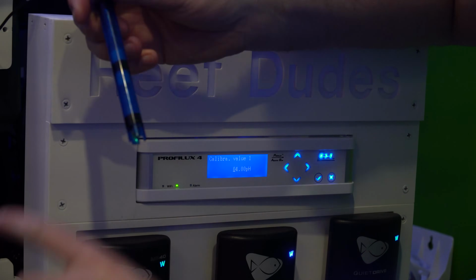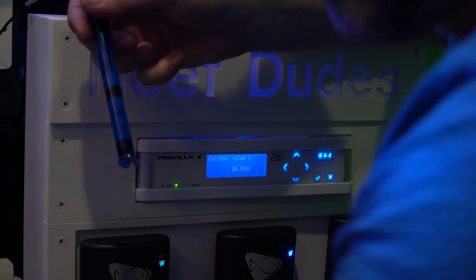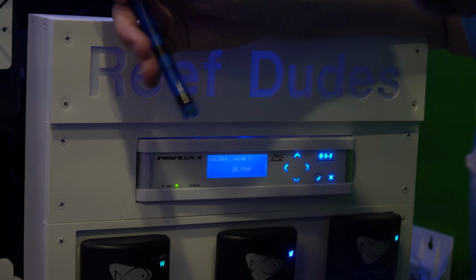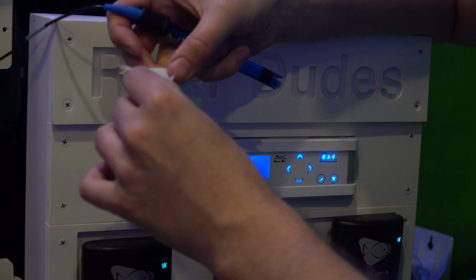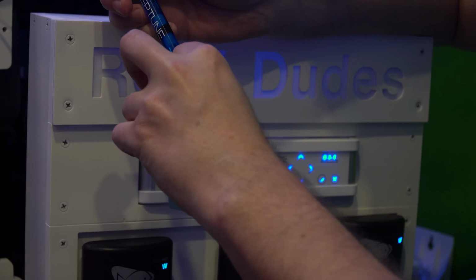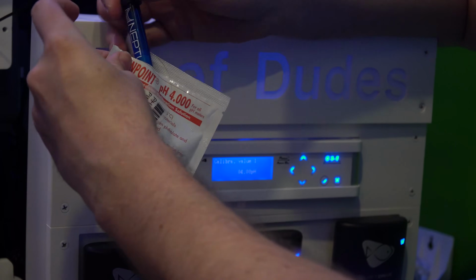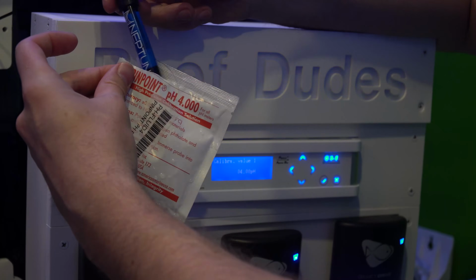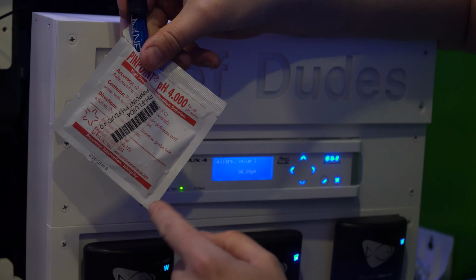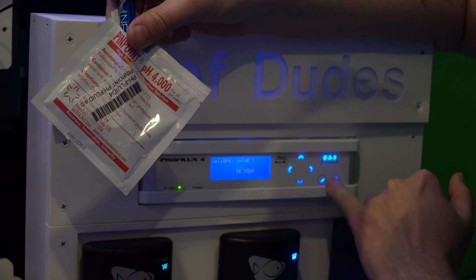All right, let's pull the cap off, and give a quick rinse in RODI water just to get off that storage solution. Open our pH 4 packet and set the probe inside. I usually give a little tap just to make sure you're getting air bubbles off and kind of put it in the kitty corner of it. Now hit the check mark.